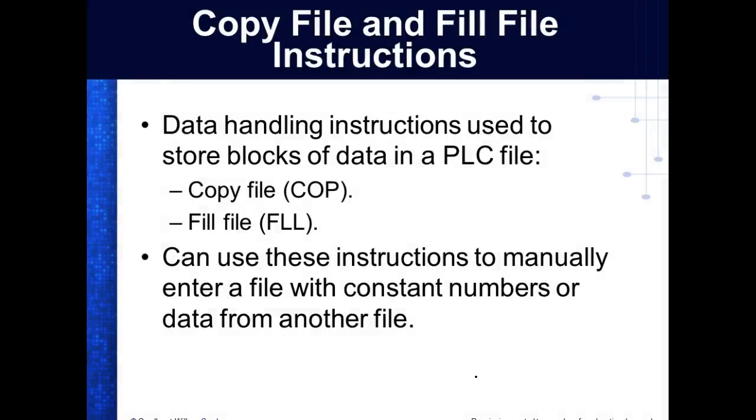Data handling instructions are used to store blocks of data into a data file. So COP would copy a group of data, and FLL would fill. We tend to use these instructions to manually enter a file with a constant number or data from a file. This gives us the ability to just shift data around, take it from here and move it to there.